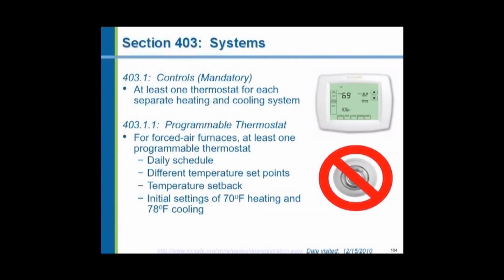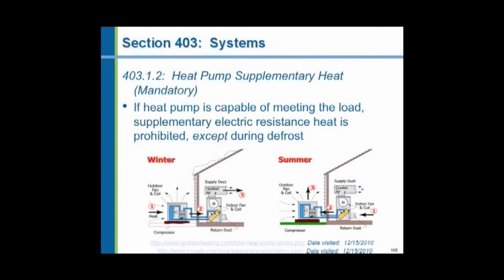First of all, our thermostats. The old snap-acting two-position thermostats are no more. The code now requires that we install programmable thermostats where we can reset the temperature at night. Heat pumps. If you have an air-to-air heat pump, the code says that you must properly size the heat pump for air conditioning the building during the summer months. However, if that same size cannot heat the building adequately during the coldest winter months, you are allowed to install supplementary electric heat. Only as much as is required, however, no oversizing. It does also allow you to install electric defrost heat. An air-to-air heat pump has to be shut down every hour or two and the evaporator coil defrosted with an embedded electrical heater, and the code allows the use of that.